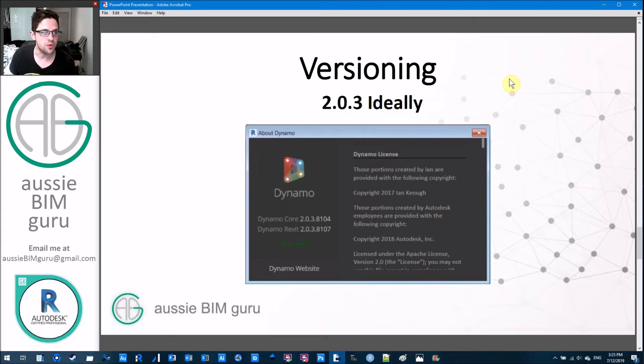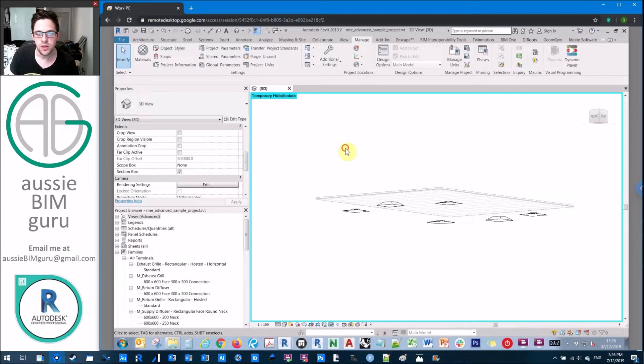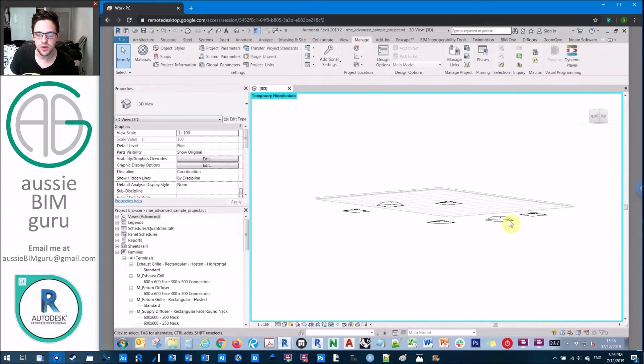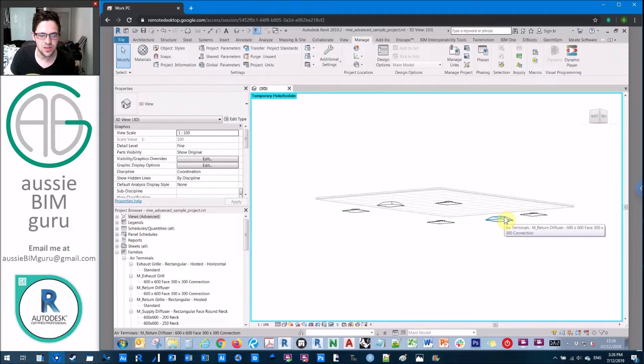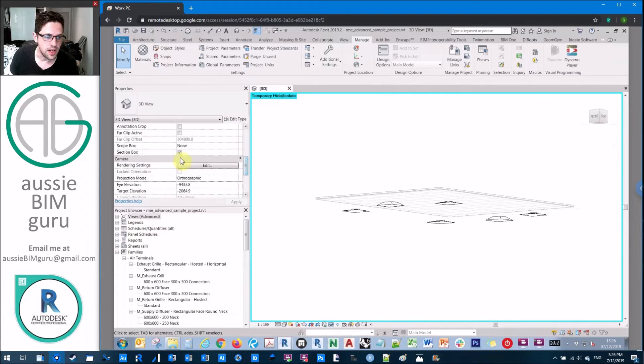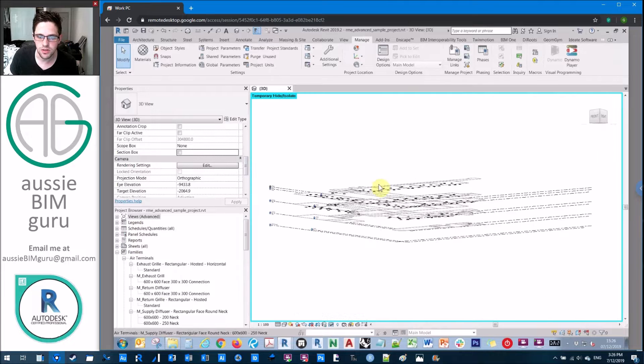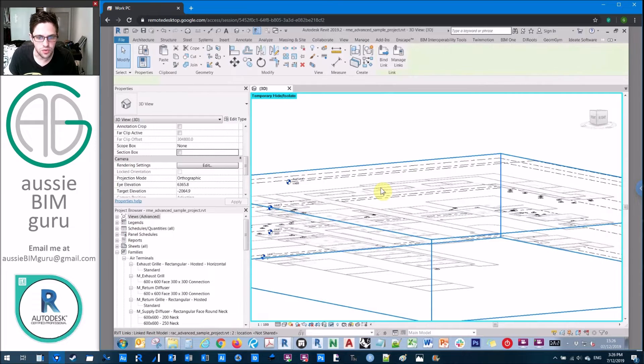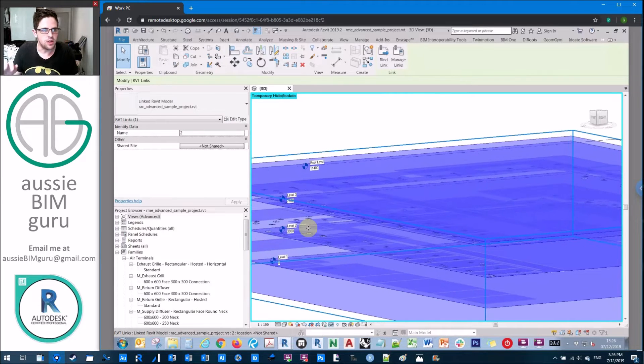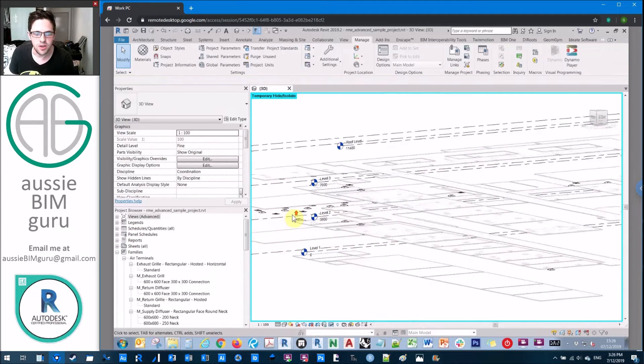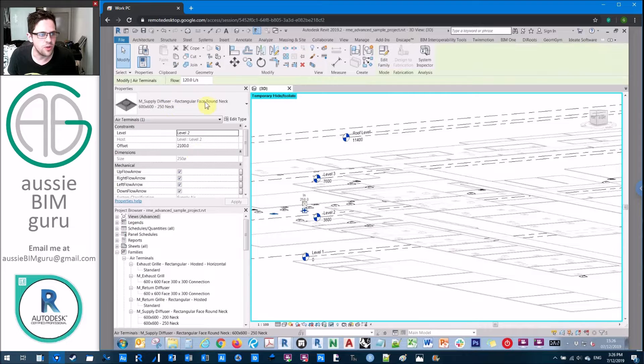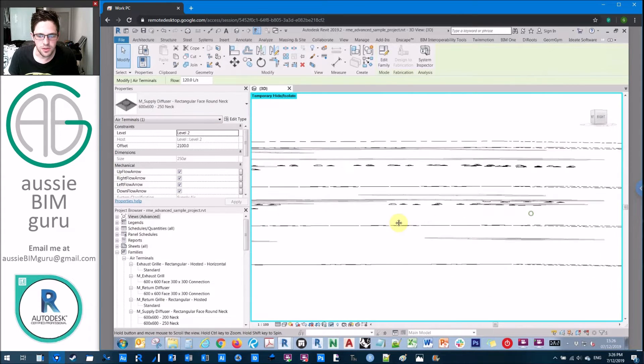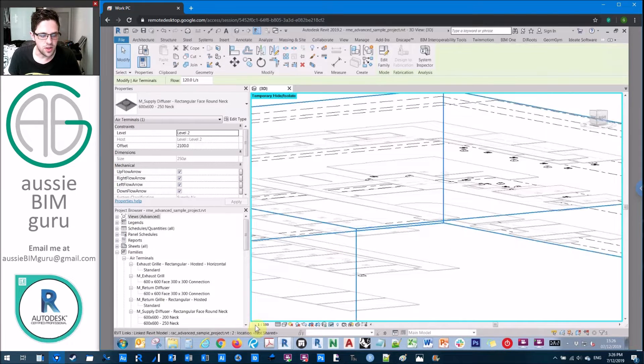So we're using Dynamo 2.0.3 in this demonstration but let's jump into Revit. So you can see here I've got a ceiling from a linked model and I've also got a bunch of registers. I'm not just going to do like six registers because obviously you get no idea of how much speed it could take to do a big model. So what I'm going to do instead is focus on an entire model. So if I turn off my section box this is the scale of what I'm dealing with. So we've got multiple floors. This is actually coming from the Revit architectural sample model and then I've actually raised and lowered a lot of the ceilings to achieve different ceiling heights. What I've done then is just made all my air terminals in this case sit at 2.1 above their host floor. So you end up with a lot of misalignments between ceilings and elements. So we're going to find a way in Dynamo to bring these together again.